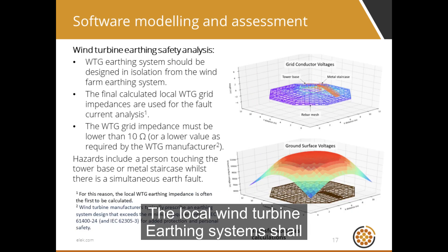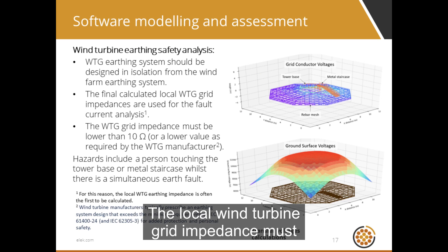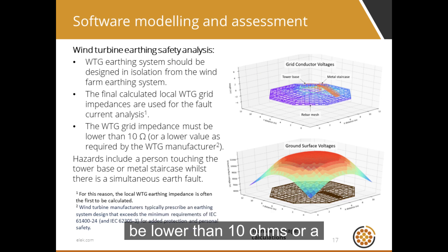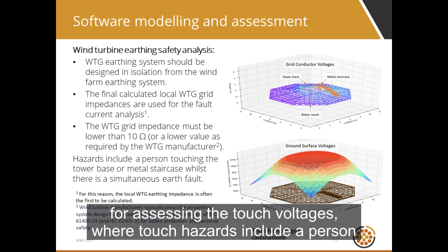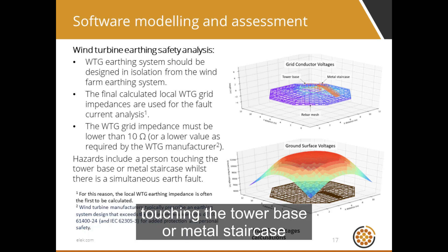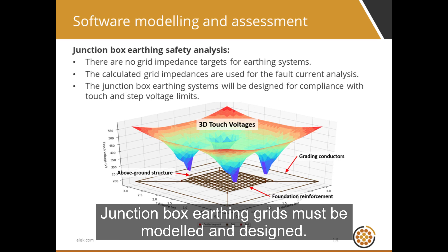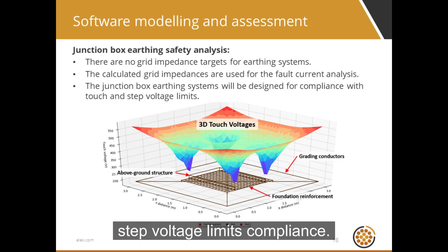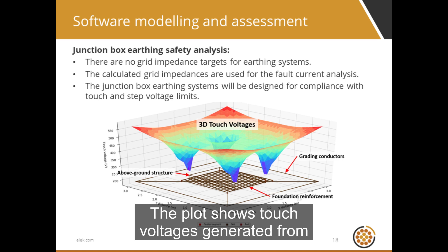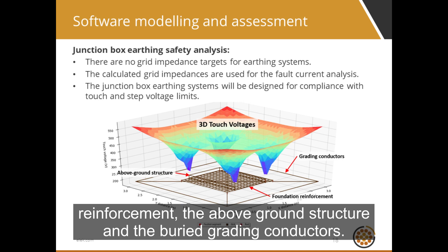The local wind turbine earthing systems shall also be designed in isolation from the interconnected wind farm earthing system. The fault current analysis uses the calculated local wind turbine grid impedances, which must be lower than 10 ohms or a lower value as the manufacturer requires. The worst-case fault currents are used for assessing touch voltages, where touch hazards include a person touching the tower base or metal staircase during a simultaneous earth fault. Junction box earthing grids must also be modeled and designed. While there are no grid impedance targets, safety must be assessed for touch-and-step voltage limits compliance. The plot shows touch voltages generated from a software model that includes the steel reinforcement, the above-ground structure, and the buried grading conductors.